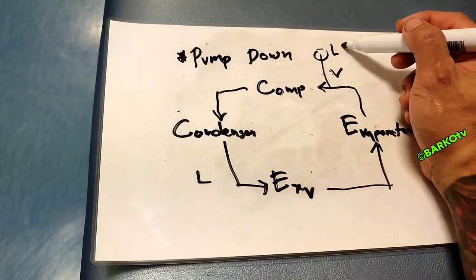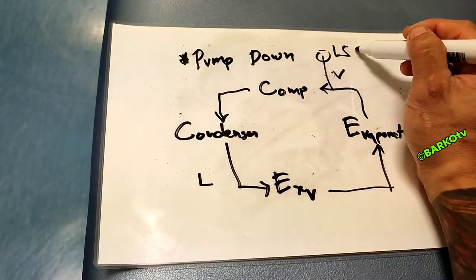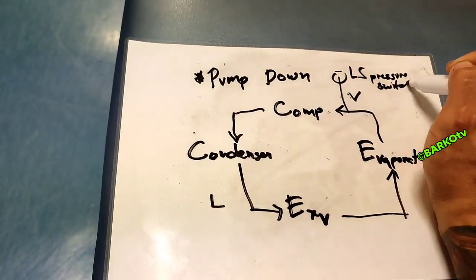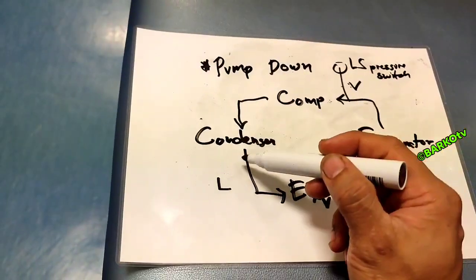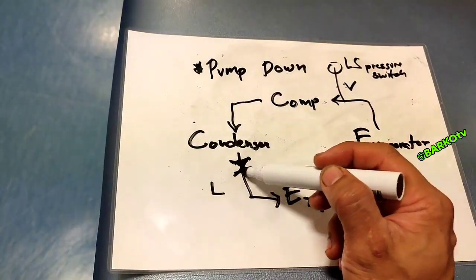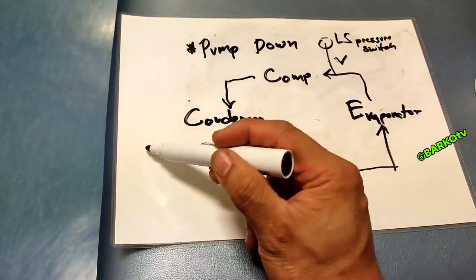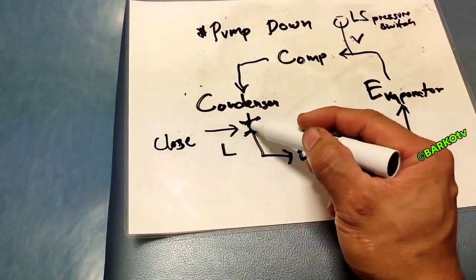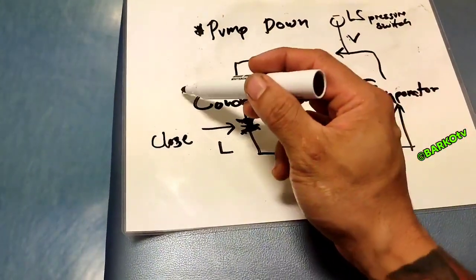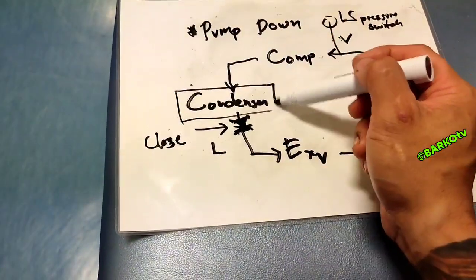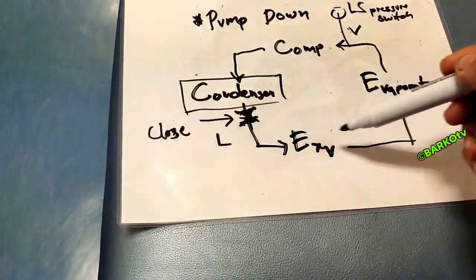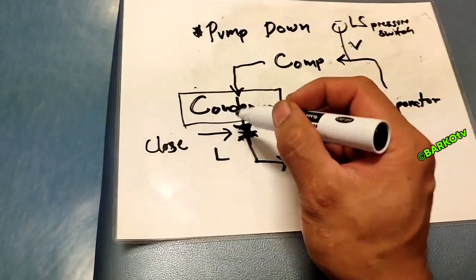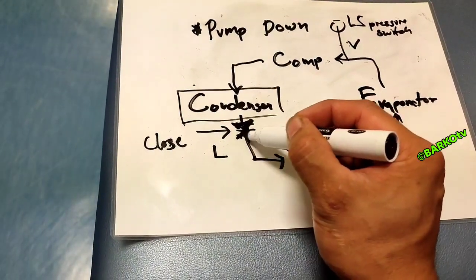On your suction side there is a low pressure switch — it acts as a monitor on your compressor side. There is also an isolation valve on your condenser. After the condenser, you need to close that valve. That is the technique for manual pumping down. If you close that valve, almost all your refrigerant in your system is collected and goes to the condenser.